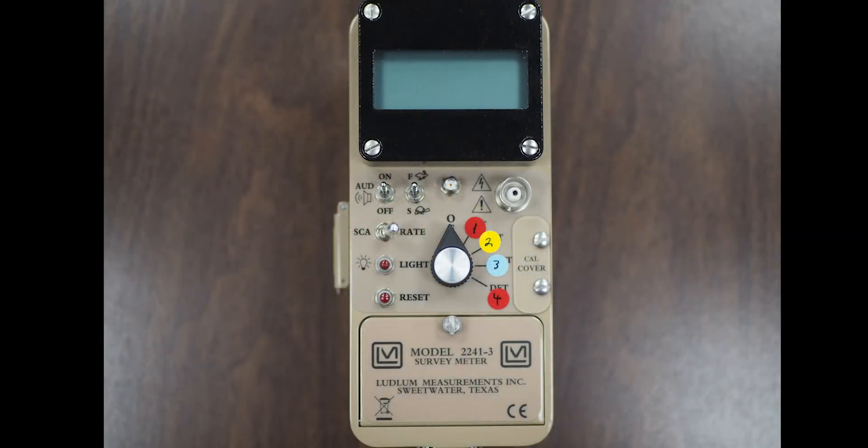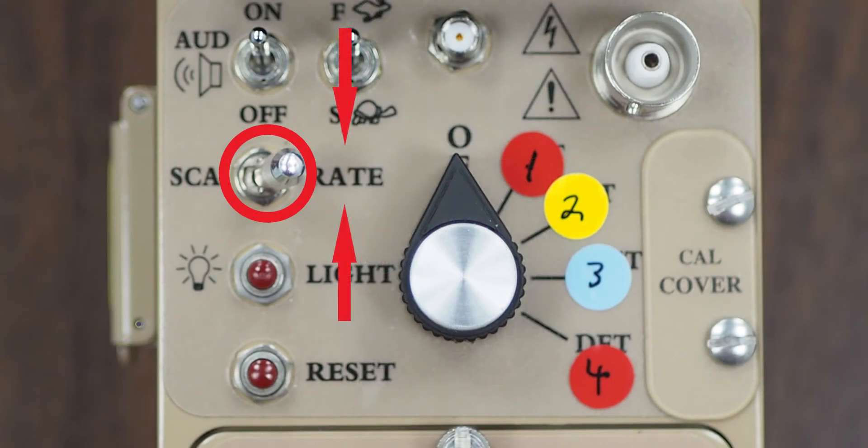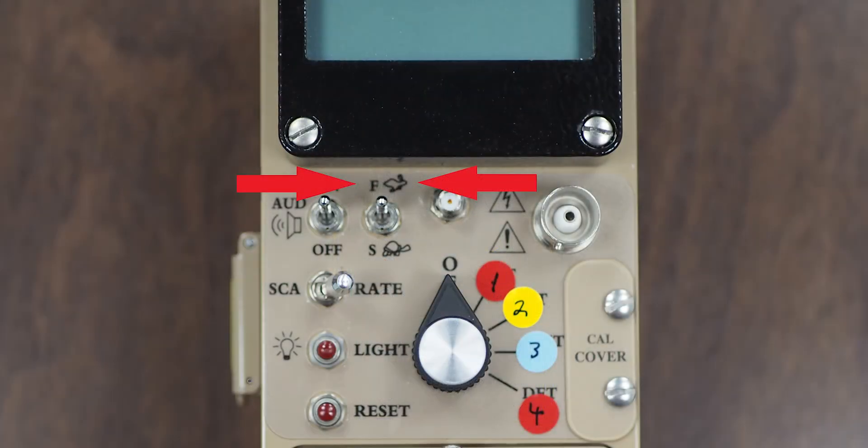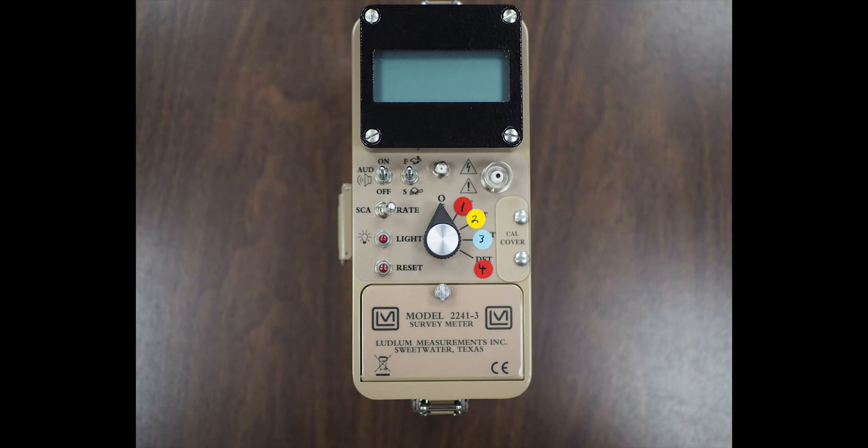A couple of notes on the controls. Most first responders typically only use the rate mode and don't use the scalar mode. By the same token, most first responders typically only use the fast time constant and don't use the slow time constant. But your local procedure should take precedent.